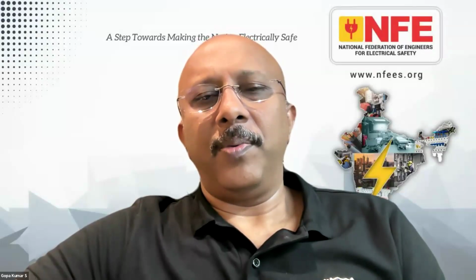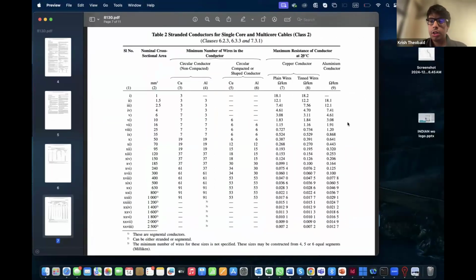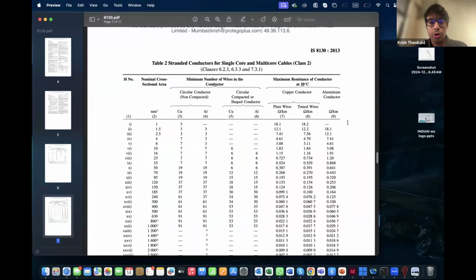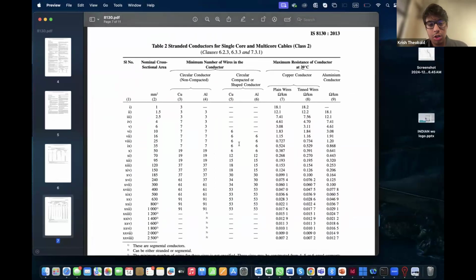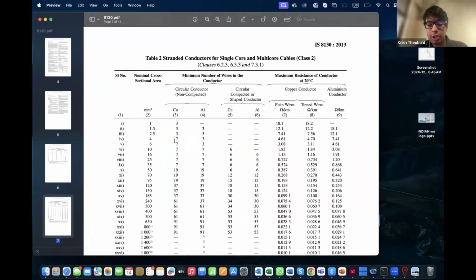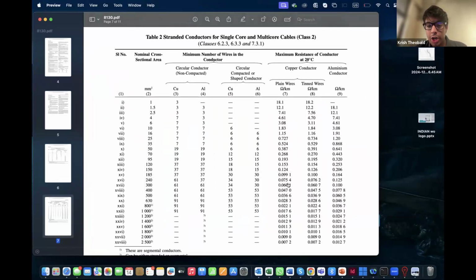I have here with me IS 8130, and for class 2 conductors it talks about conductor resistance. So, for example, if you consider a 300 square millimeter copper conductor, I have in front of me IS 8130, the standard that talks about conductors in insulated cables. It mentions that a 300 square millimeter plain copper conductor will have a resistance of about 0.0601 milliohms per meter, or ohms per kilometer. So what we do in India is we add this to the impedance of the transformer.